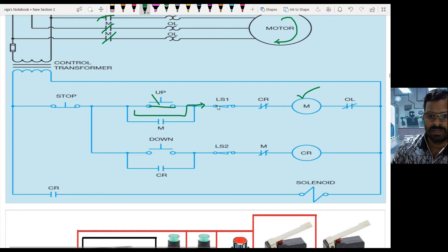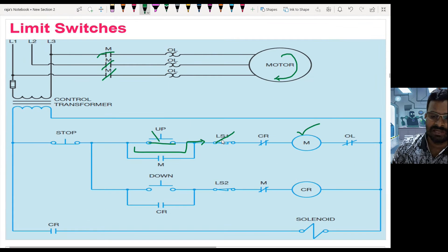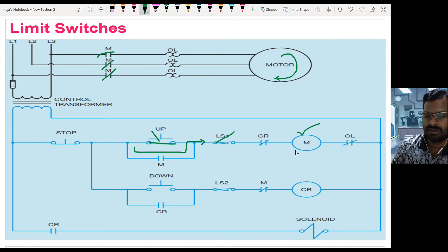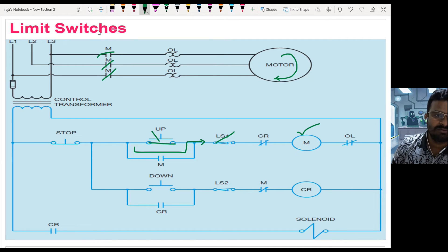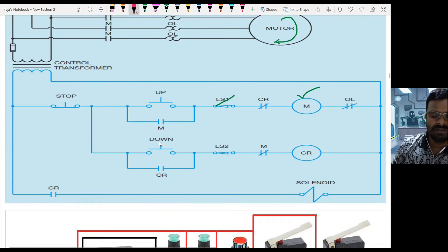When the cylinder reaches LS1, since it is a normally closed switch, this limit switch opens. When this opens, the coil gets de-energized automatically, and when the coil is de-energized, the contacts of the pump contactor turn off and the current flow stops.